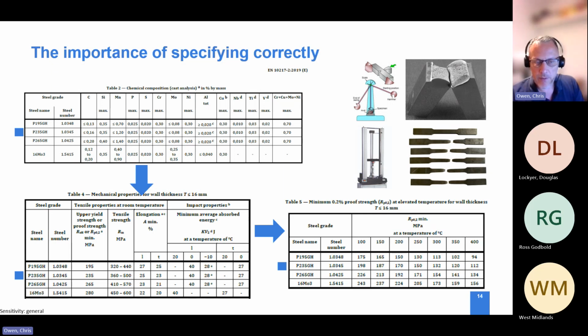Table 4 also defines the different testing requirements in terms of ductility. We do what's known as a Charpy impact test, shown in the top right image - we take a section of tube and do room temperature and low temperature impacts. Depending on what grade you're specifying, there might be different lower impact temperatures. And then we've got tensile tests, done again at room temperature and also elevated temperature.